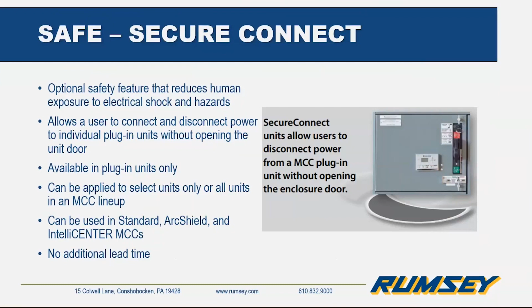And here is a mechanical breakdown of how exactly this works. So once your disconnect handle is in the off position, you use a 1/4-inch hex socket wrench. There's a little insert shaft port that you'll see there. You turn that a 1/4 turn and put that to the disconnect position. And what that does is it unplugs the power stabs from the vertical power bus and retracts them into a stab housing. And once the power stabs go into that housing, a continuity circuit is completed. And you can test that through the status port that you see on the top, there's a picture there on the left.